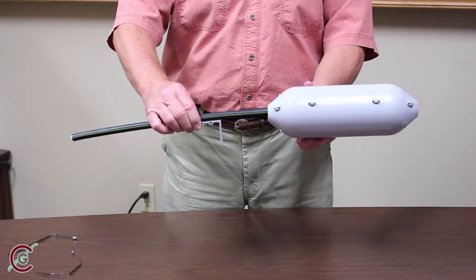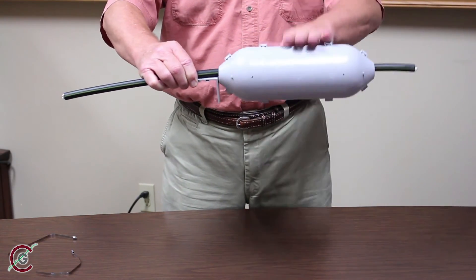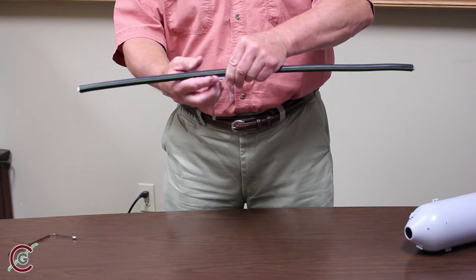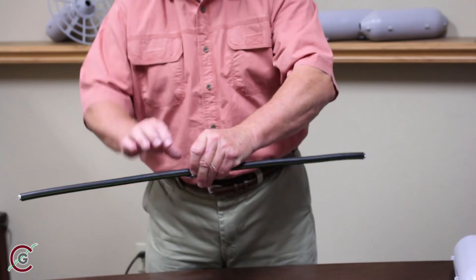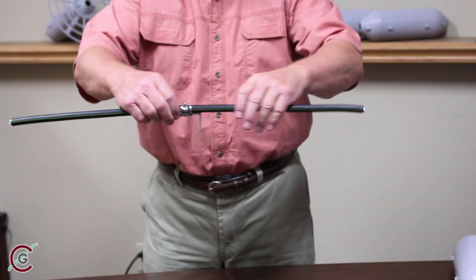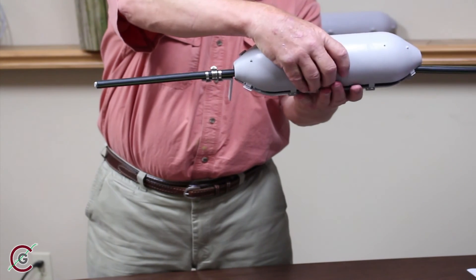Slide all five rollers with attached wheels next to the initially installed L bracket. The final step is to install the second L bracket as you did the first one. Make sure the smooth flat surface rests against the fifth roller and that all rollers spin independently without binding.